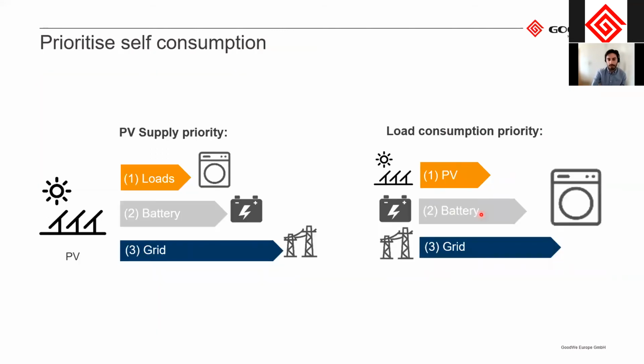Here you can see the load prioritization, the logic behind the system. If we look from the PV side, where the energy from the PV that's produced goes, the inverter tries to prioritize your loads. When the loads are fully covered, it charges the battery. In case both the loads and the battery are covered and the battery is fully charged, the excess power is exported to the grid, in case you haven't set up a power export limit. For the load consumption, it firstly takes the power from the PV, secondly from the battery, and thirdly from the grid. This is to optimize self-consumption.